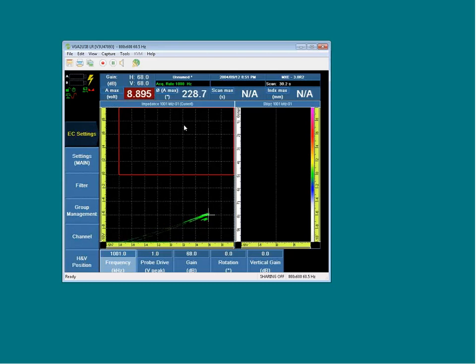So the idea here, while we're producing that liftoff, so I'm actually tapping the probe against the sample, that's generating liftoff from the cross there, that's the null point, to the air, which goes right now outside the screen. What I need to do is set that rotation angle, so my liftoff is going to look flat, and when we say flat, it means going to the left. Any eddy current knowledgeable person will be used to performing that step to set up the liftoff. Many instruments like the Nortec 500 have an auto liftoff feature that allows doing that automatically. OmniScan does not have that, but it's very easily done, as you saw with the rotation control. So once I have that liftoff, I'm ready to scan.